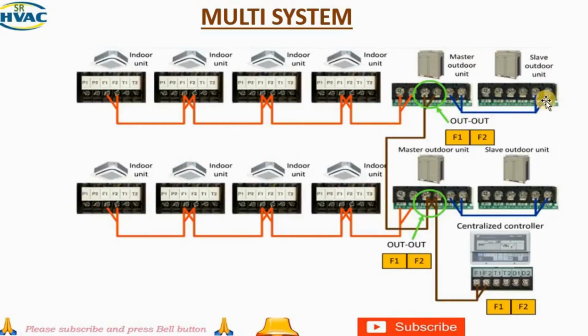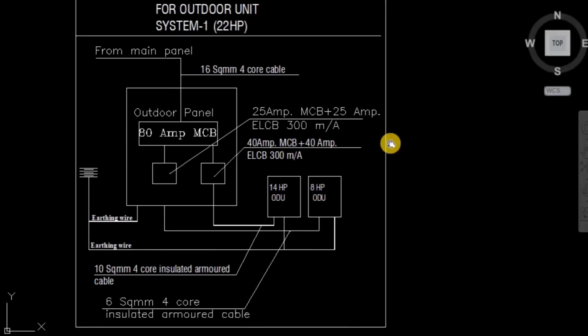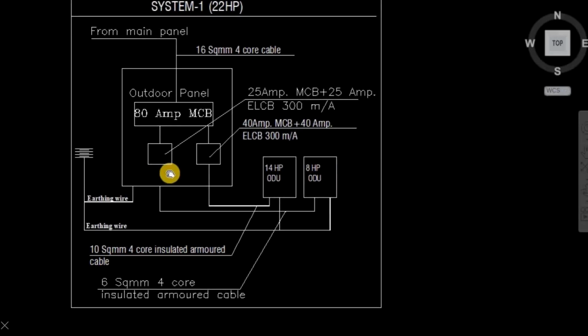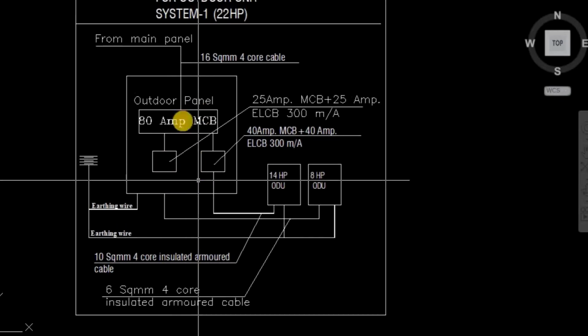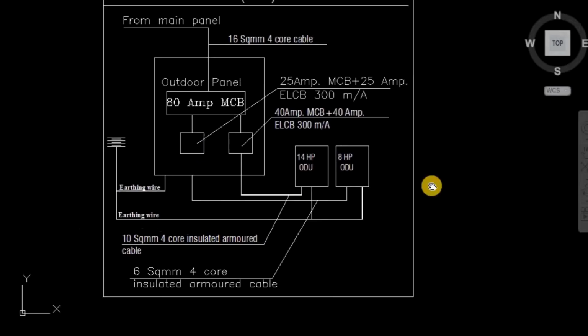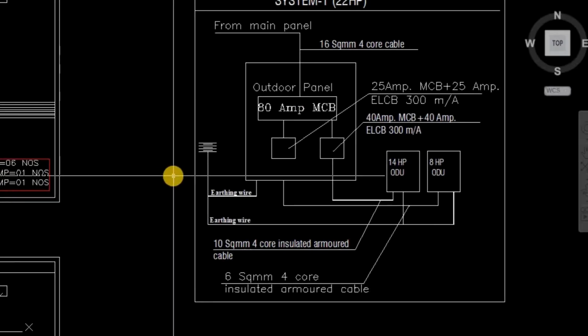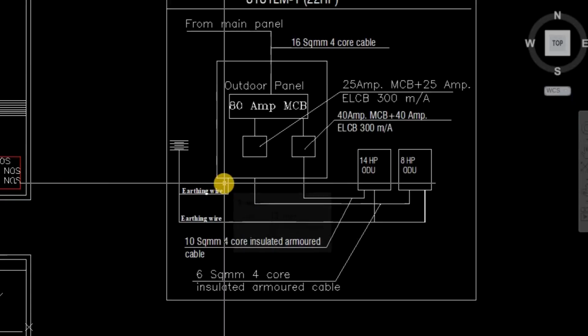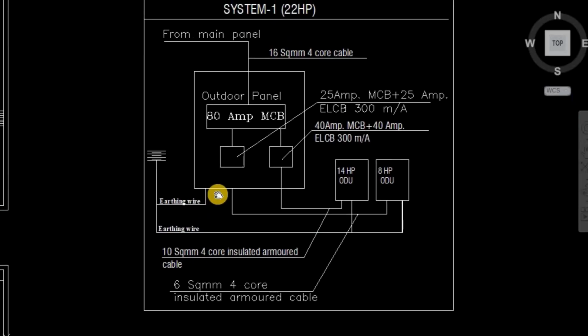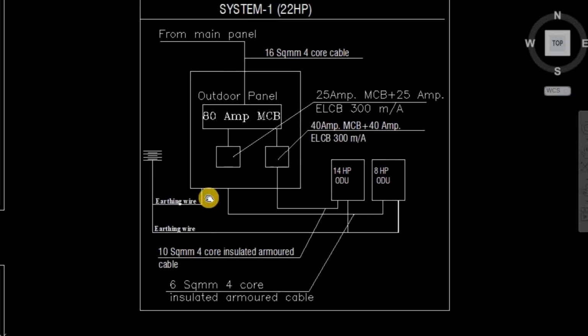Here you can see this is disconnected. Okay, this is the central wire coming. You have a central control system. Okay, this is connected to it. This is how multi-system wiring is done for communication. I hope you have cleared this. Friends, some of the key electrical components of a Daikin VRV system include the main terminal, the terminal block for indoor units and the controlling wire terminal for communication, and the fuse breaker panel for circuit protection. Each of these must be wired correctly for the system to work efficiently.